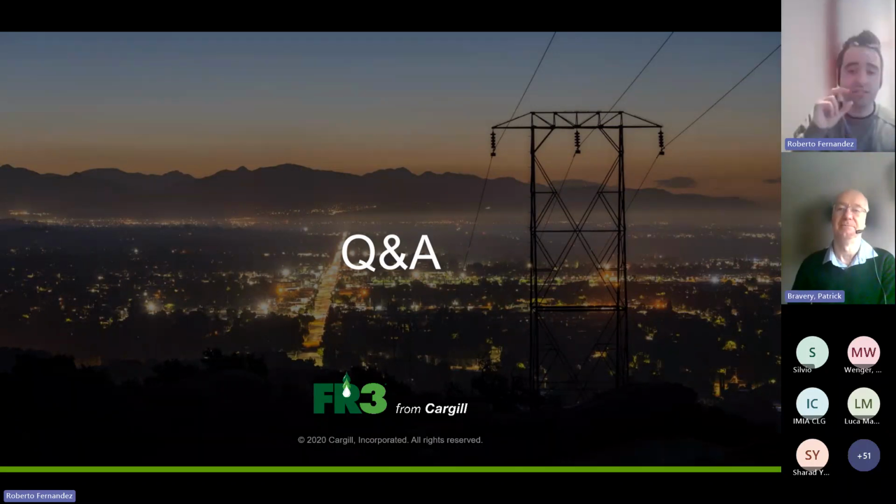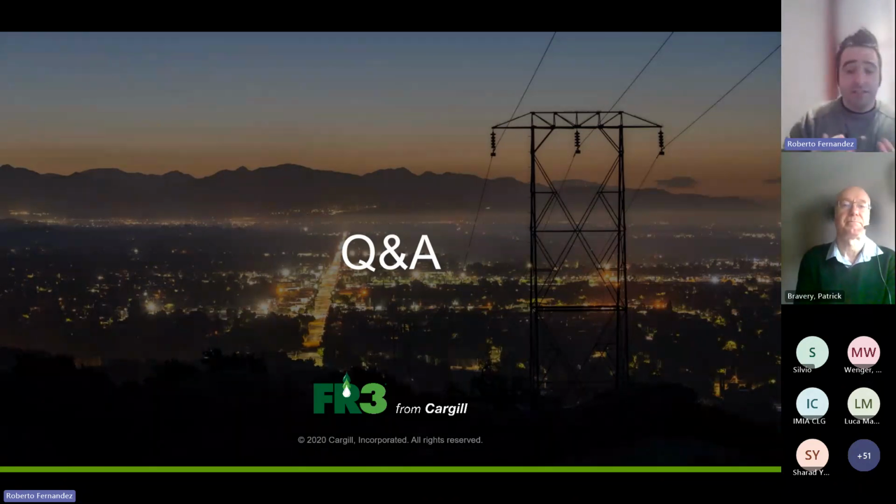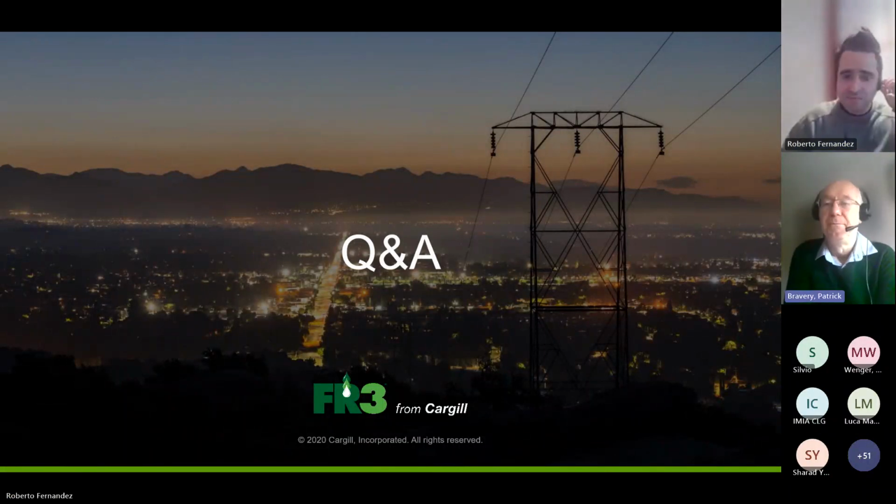The first one is at which stage of the aging of the transformer the retrofilling is done, because we are also extending the life of the asset. So if the remaining life with mineral oil is 10 years, maybe we can extend it to 15 or 20 years. So all the investments are delayed, and you have additional time to make the compensation. It's also a balance between the benefits that you get from the insurance companies and, at the end of the day, a risk mitigation plan that is put into place. So it's not a straightforward answer. Okay, no problem.